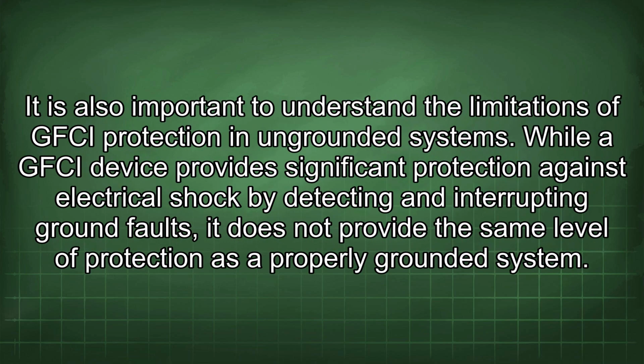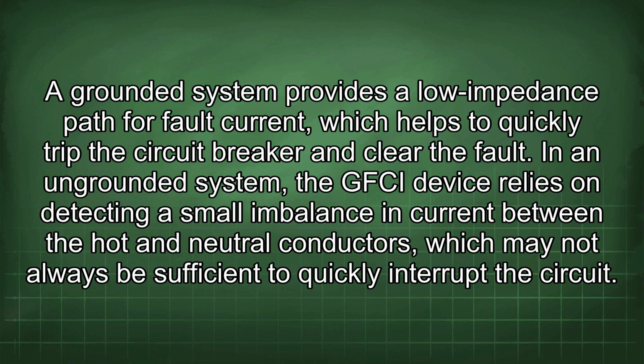It is also important to understand the limitations of GFCI protection in ungrounded systems. While a GFCI device provides significant protection against electrical shock by detecting and interrupting ground faults, it does not provide the same level of protection as a properly grounded system. A grounded system provides a low impedance path for fault current, which helps to quickly trip the circuit breaker and clear the fault. In an ungrounded system, the GFCI device relies on detecting a small imbalance in current between the hot and neutral conductors, which may not always be sufficient to quickly interrupt the circuit.